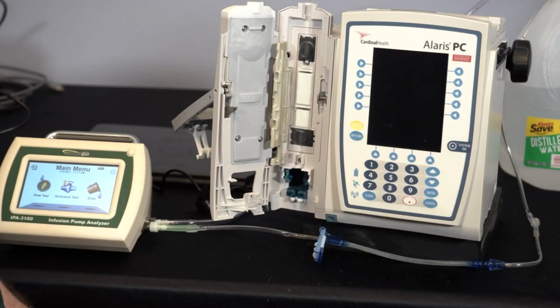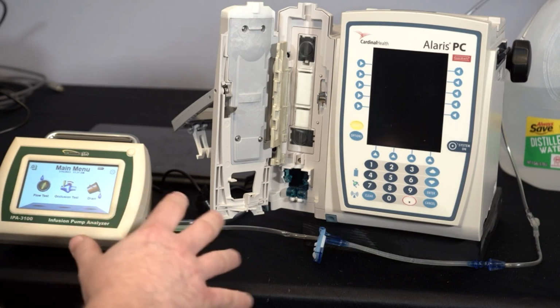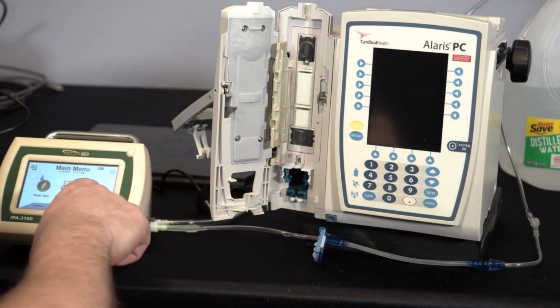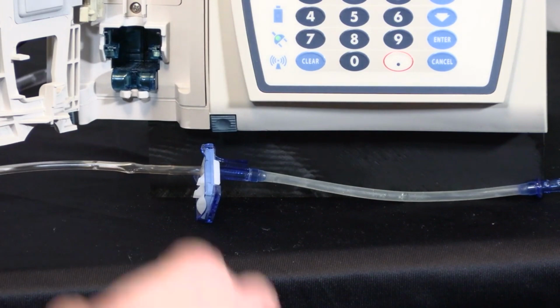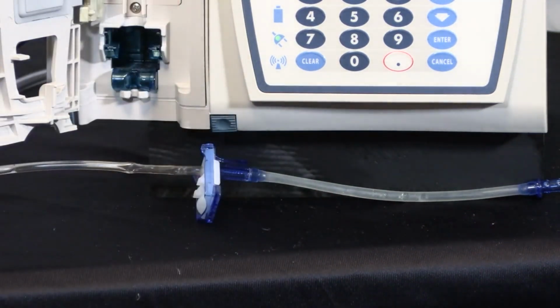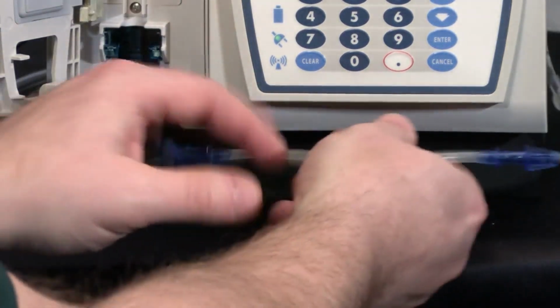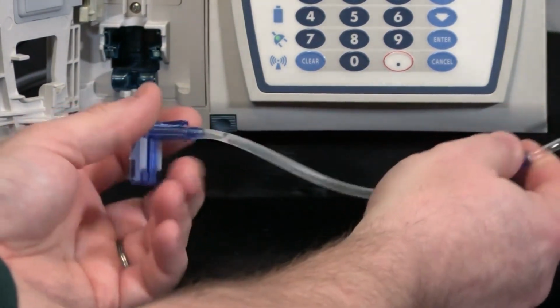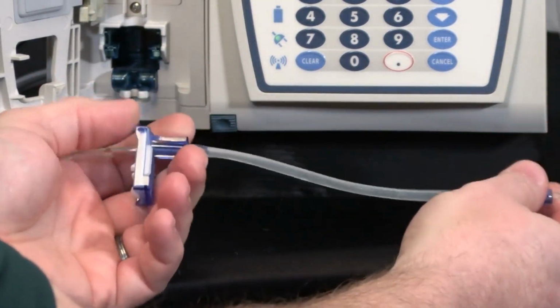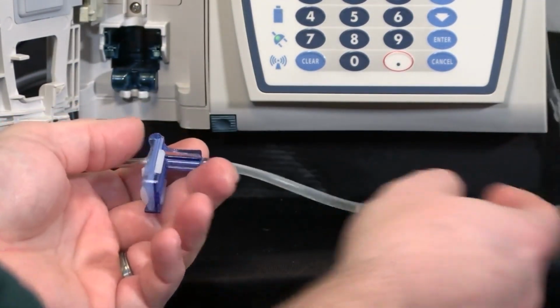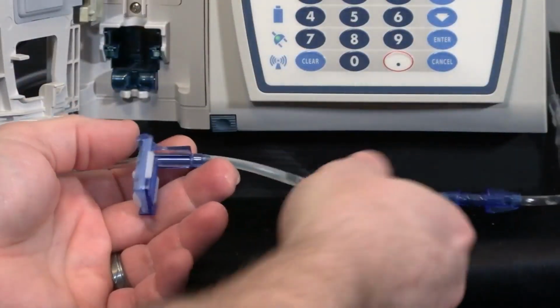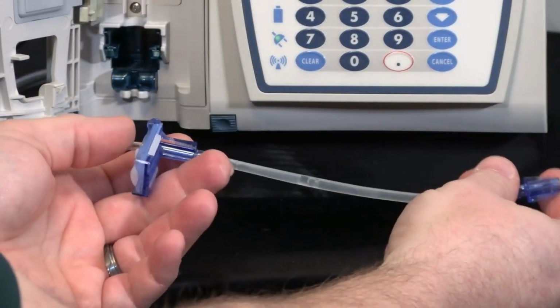Before we can run a flow test, we need to prime our pump. So I'm going to show you a cool feature that we have built into the IPA 3100. If we actually go to the drain mode, that will force fluid to be pumped through the unit. And if you've ever worked with the Alaris pump before, you'll know, and most infusion pumps, they're very sensitive to bubbles. So we have to prime the tubing in order to make sure we get all the bubbles out of the system.